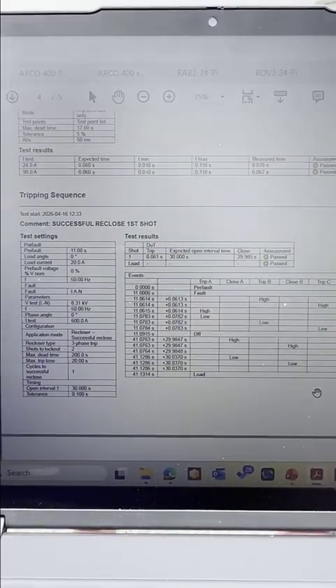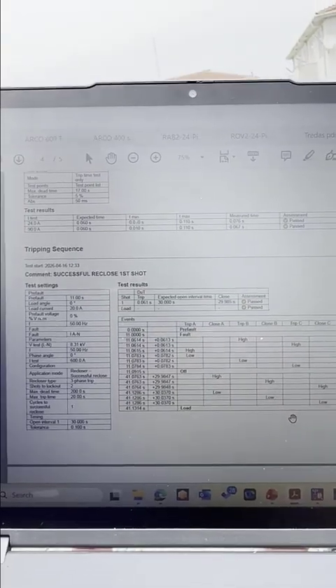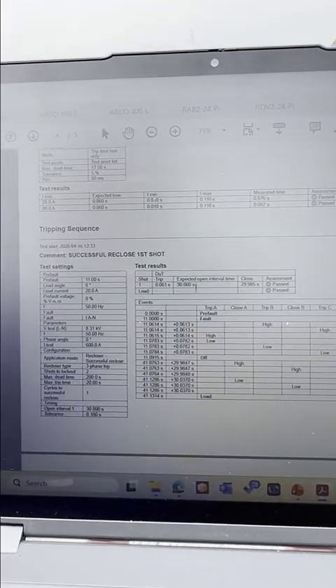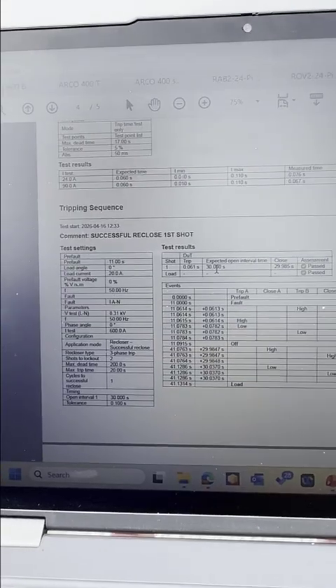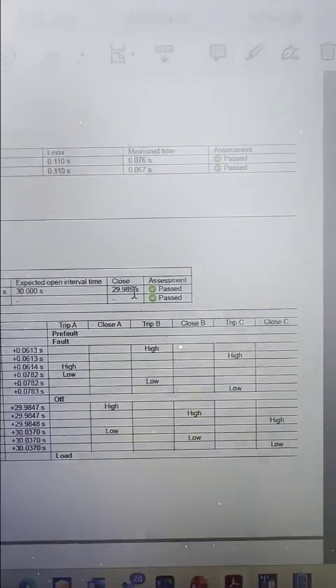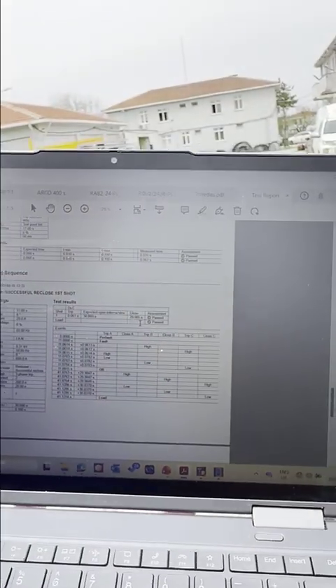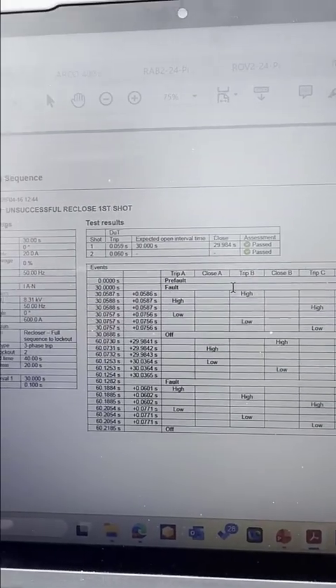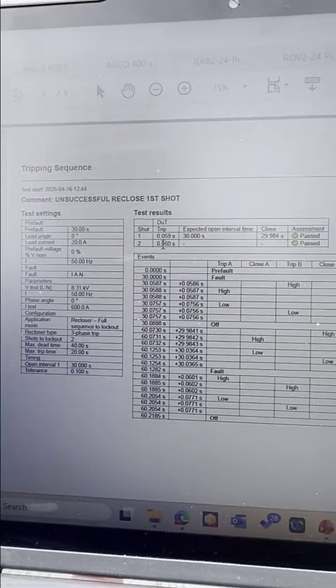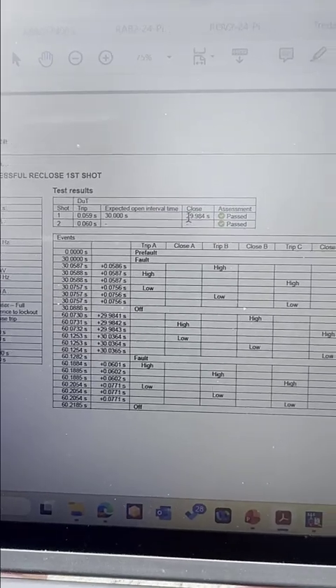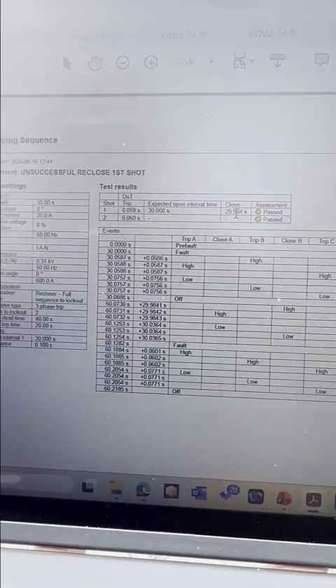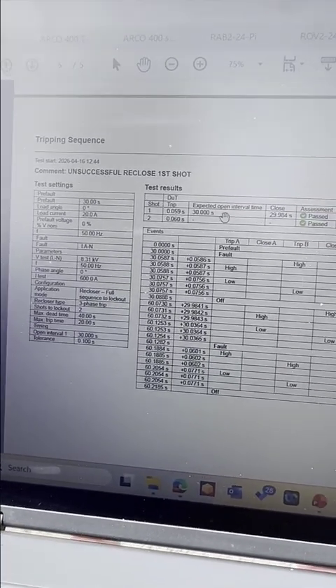And then we have the tripping sequence. We tested the successful recloser for the first shot. Here you can see the expected open interval time is 30 seconds, and the measured is 29.985 seconds. Also you can see the unsuccessful reclose or the lockout reclose. So we have two trips, first trip, then the first reclose after 29.984 seconds, and then the second trip and the circuit breaker locked out.